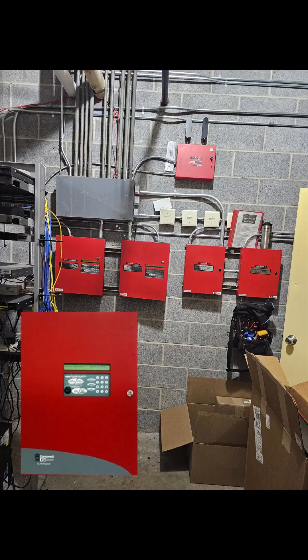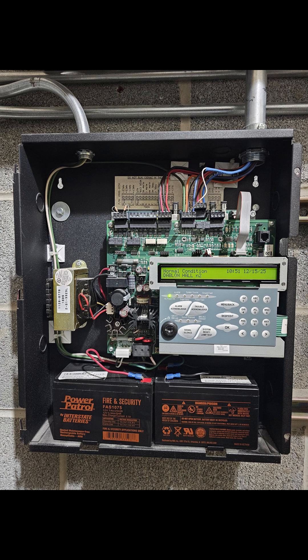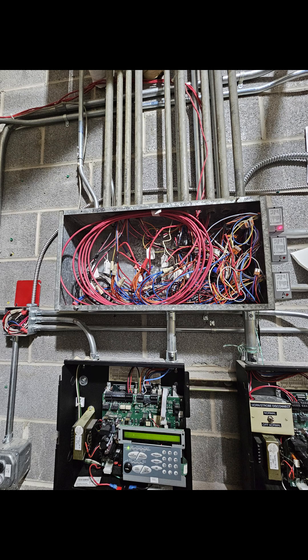The existing system is an FCI 7100 system with two nodes. What we're going to need to do is take these panels down and replace them with a two-node E3 system. Having this wireway above the fire alarm panels will simplify this process.